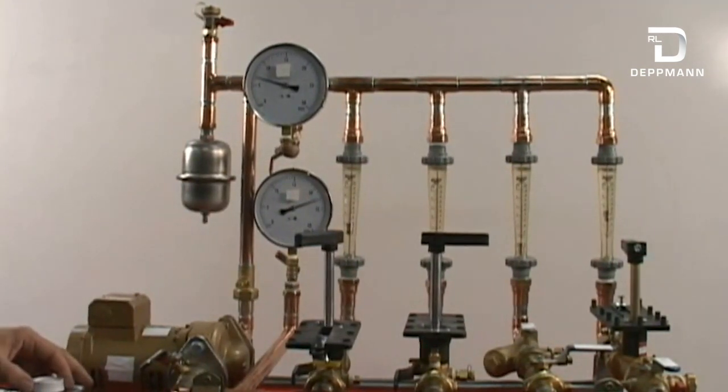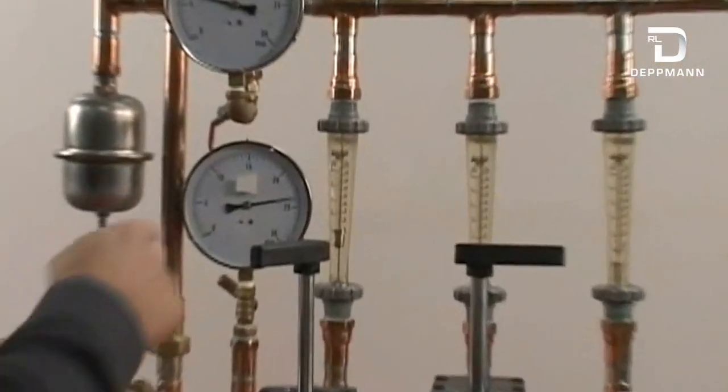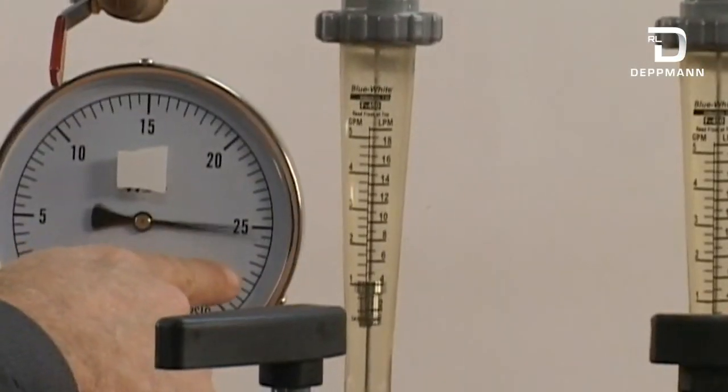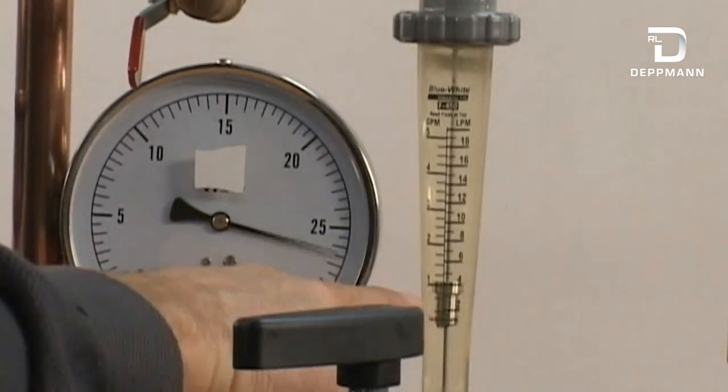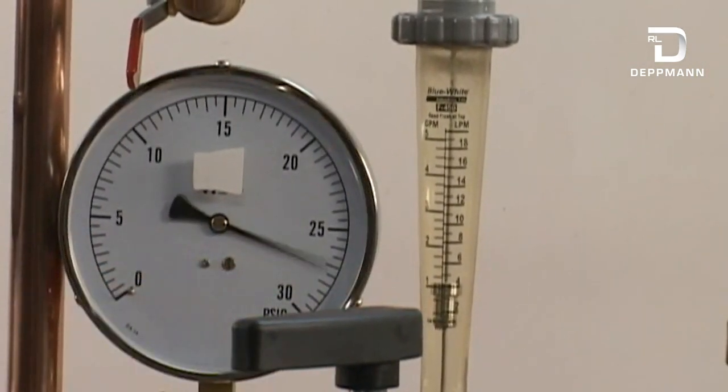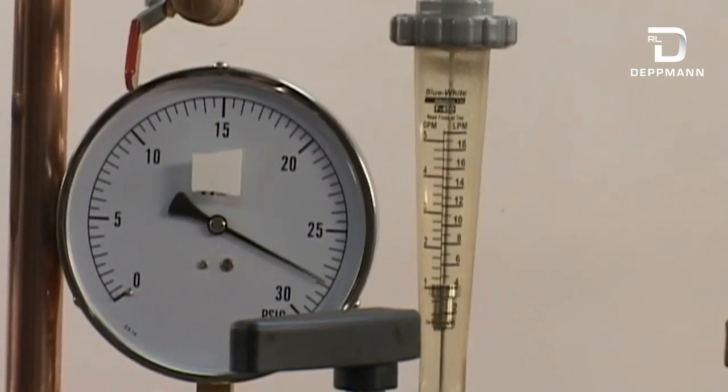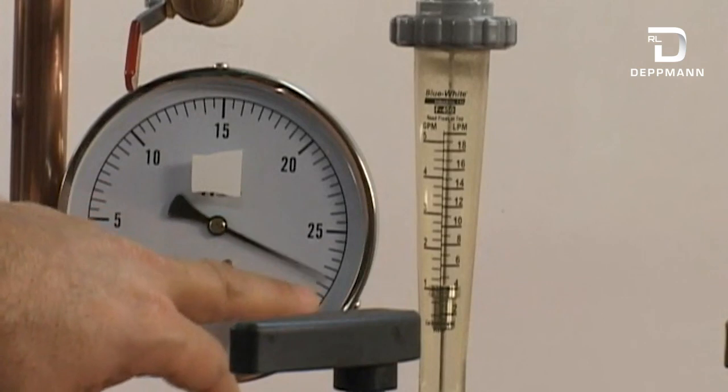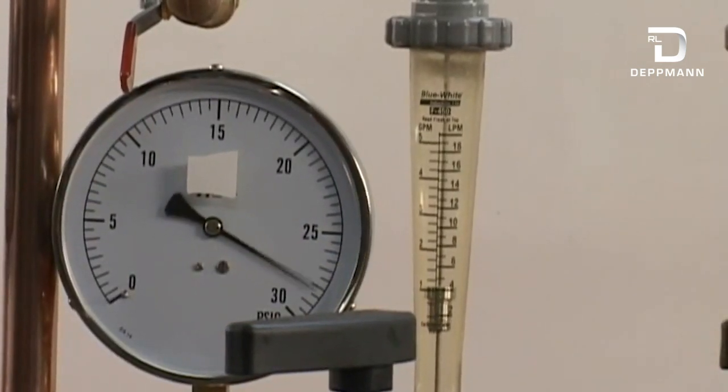So as I ramp this up, I want you to zoom in on that and watch. I'm going to ramp this up. As you see, my discharge pressure is going up, but my flow is staying at 1 GPM. It's going up. See that? So now I'm up around 28 pounds, that stayed at 1 gallon per minute.